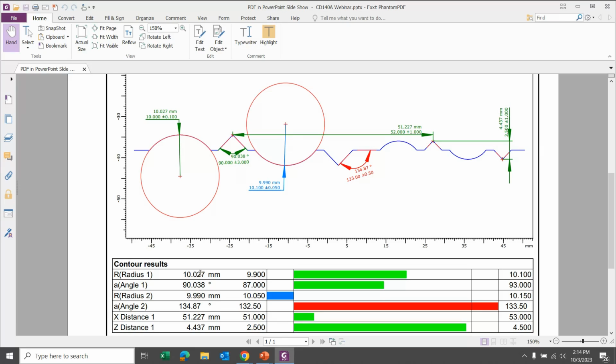By default, if the measurement is within your tolerance, it will show up green in both the chart and on your screen, in your evaluation screen. If your measurement is perhaps too small, this is your instant indicator whether the sample is good or bad.